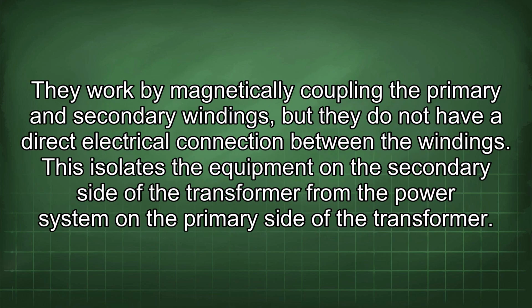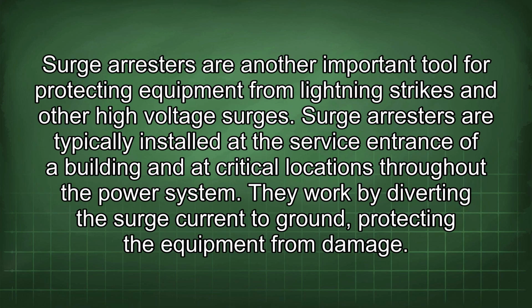They work by magnetically coupling the primary and secondary windings, but they do not have a direct electrical connection between the windings. This isolates the equipment on the secondary side of the transformer from the power system on the primary side of the transformer. Surge arresters are another important tool for protecting equipment from lightning strikes and other high-voltage surges.